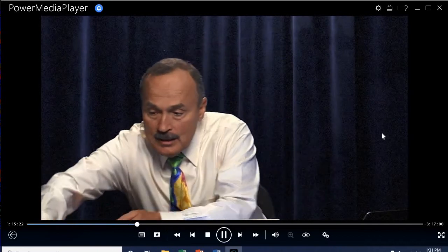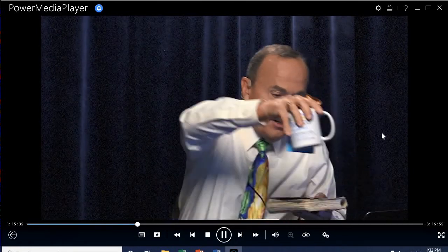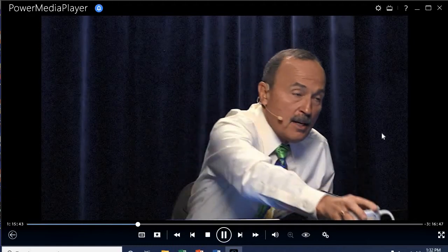In other words, here is my breaker, and here are all the things that go with this. Then all of a sudden you get it, and you've got this box with all kinds of things inside, right? Well, these other things were never part of the listing and labeling instructions. Now, what do we do? We don't have the information on what the listing and labeling instructions were, so we kind of assume that what came with the packaging must be the instructions. And that's what inspectors are going to do.